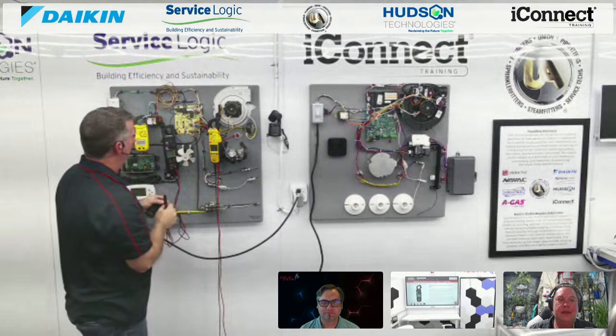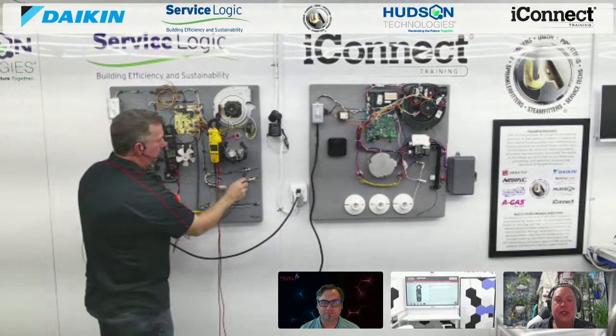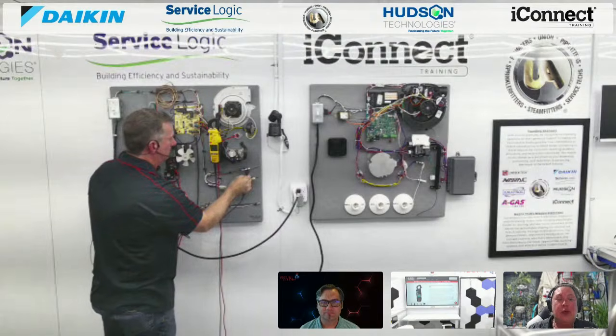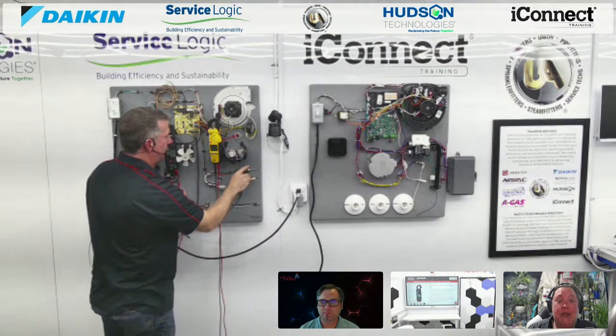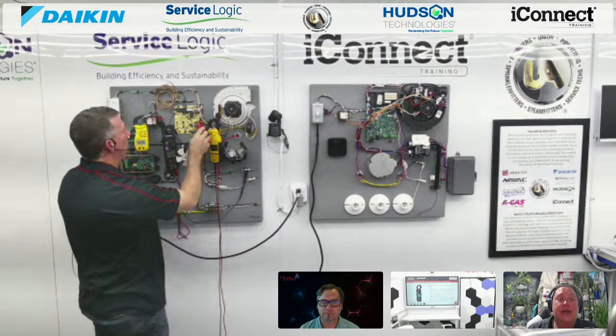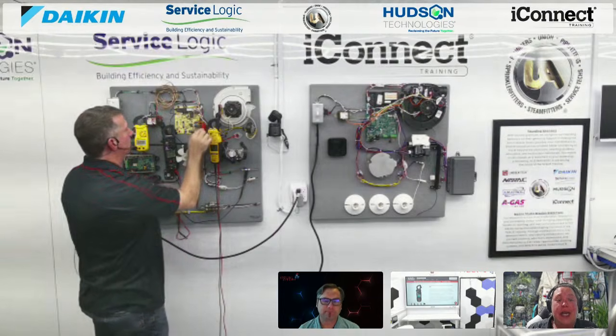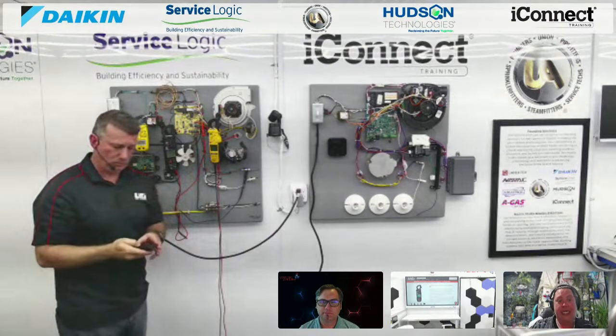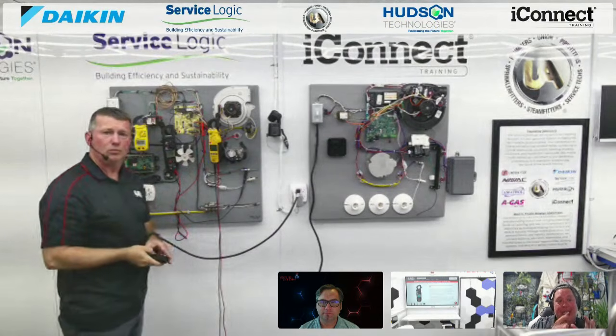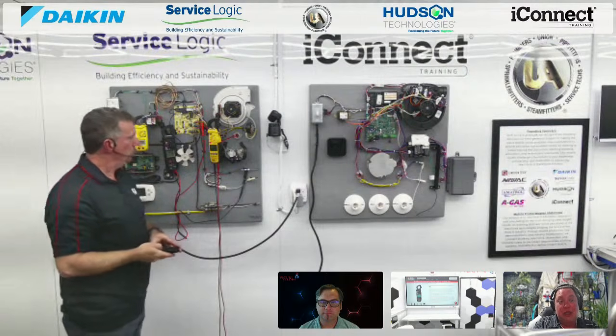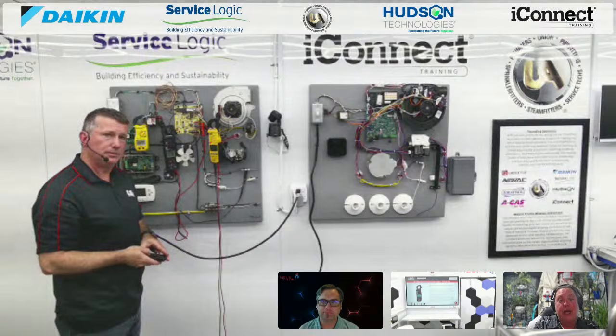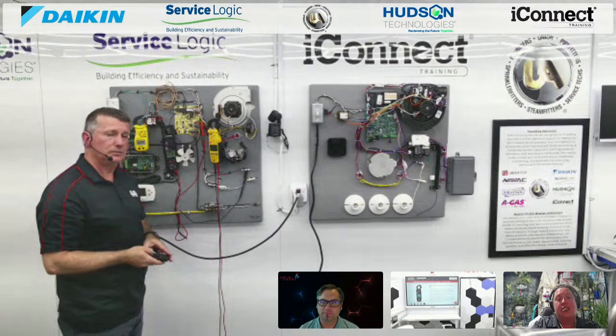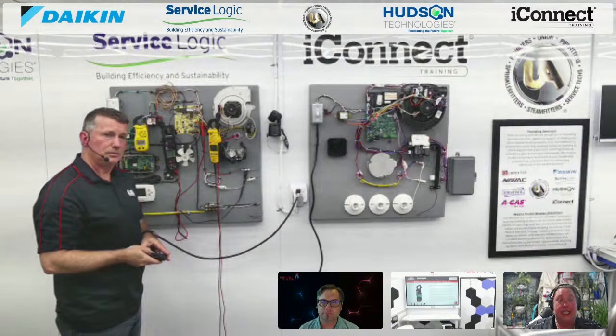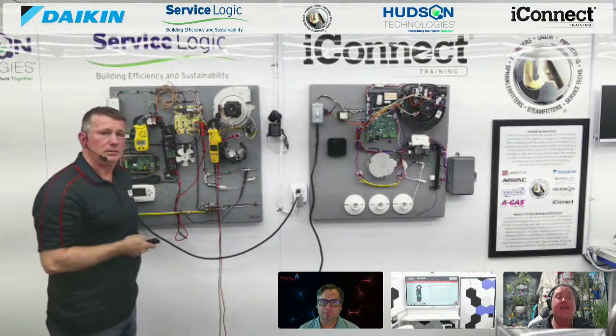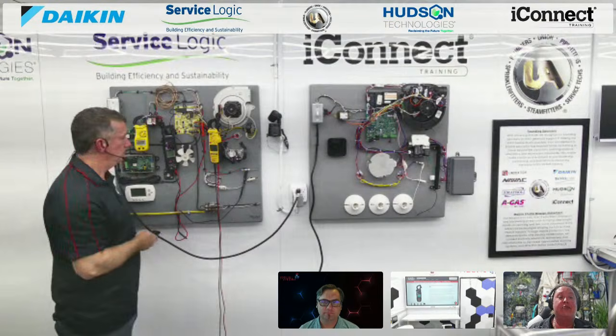The easiest way to think about it is it's going to bleed out those ghost voltages. There's a resistor built into it that bleeds it out. So where it looks like it's jumped those lines and you're chasing it, now it's going to put a bit of a load onto that signal and bleed it out so you're not chasing it. Instead of seeing the half, you should see it resume to the normal 0.